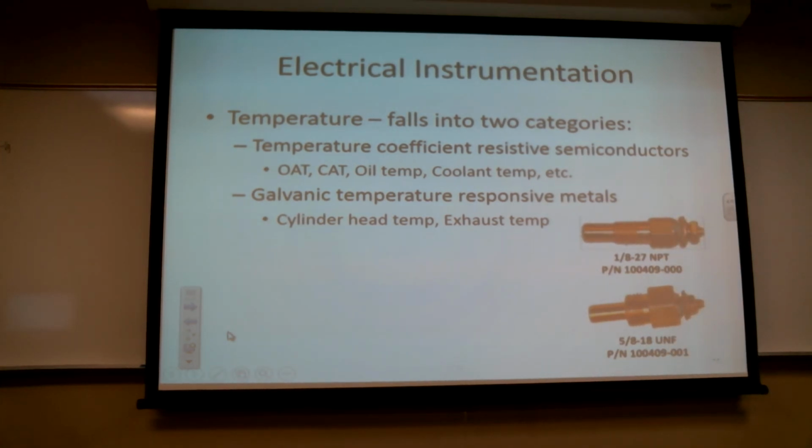I will say, though, that because these things operate in the millivolt range, any funky connections, any corrosion, any slight distortion there, cause them to misread greatly.